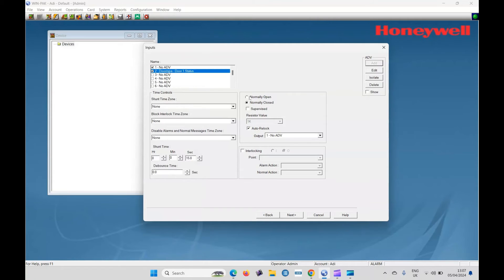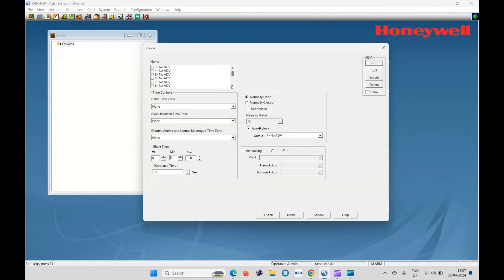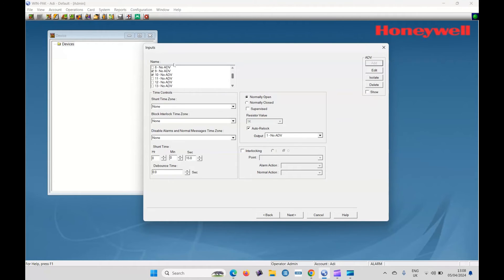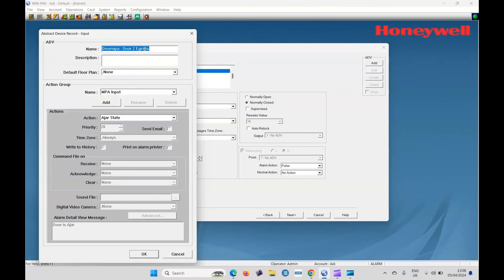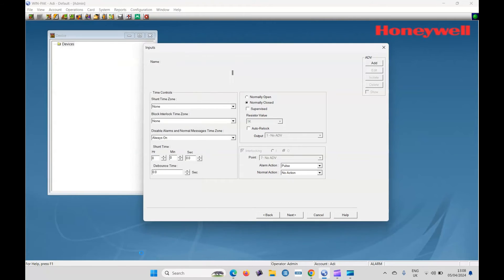I'm going to use a different type of contacts. I'm using micro switch. So let's change that to normally open. And then as I said, there's eight inputs. So if we then go down to input nine, input nine will be door two input one, which should, if I clicked add, should come up as a door two exit button. Click okay. So they're the inputs.